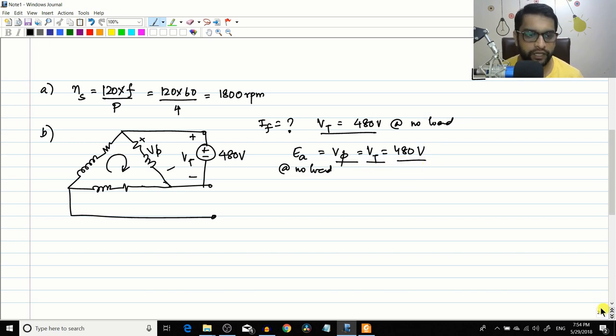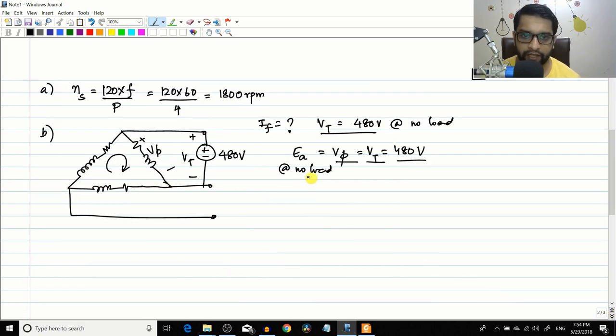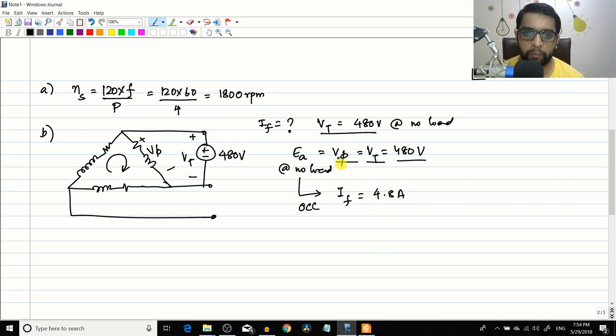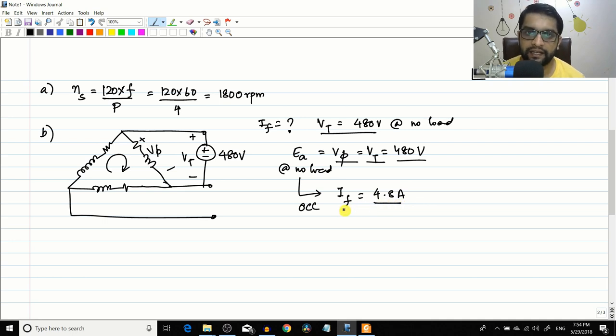Plotting 480 volts on the OCC, we read from the book that the corresponding field current IF ≈ 4.8 amperes. This means if the generator is rotating at 1800 RPM and you supply 4.8 A as field current, the terminal voltage at open circuit will be 480 volts.